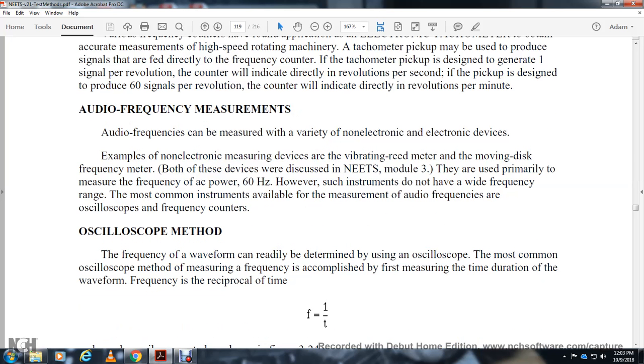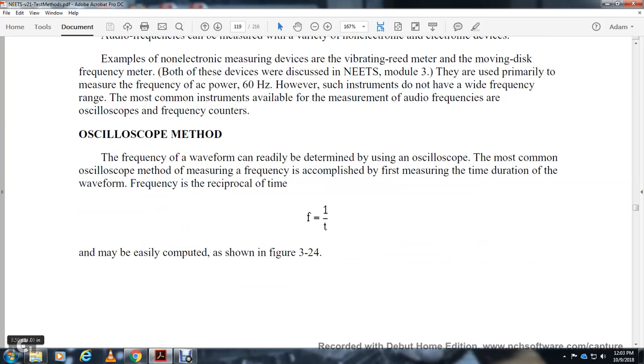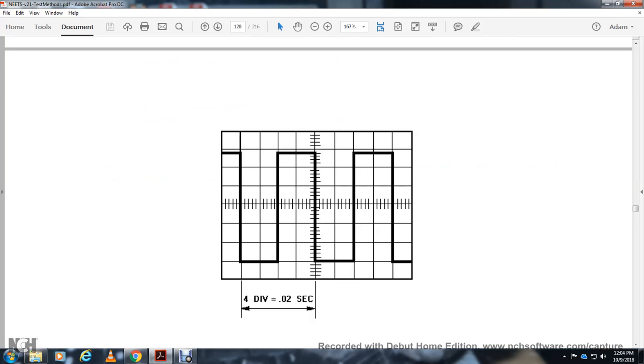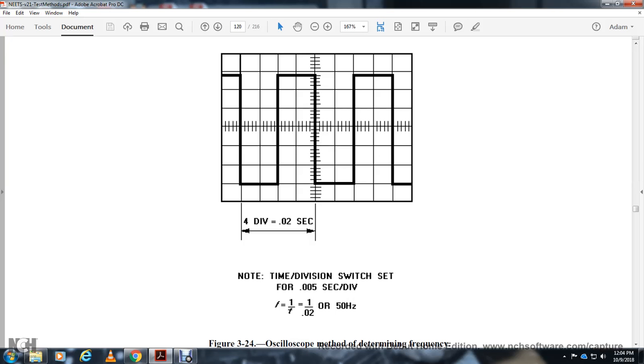Oscilloscope method. The frequency of a waveform can readily be determined by the oscilloscope. The most common oscilloscope method of measuring frequency is accomplished by first measuring the time duration of the waveform. The frequency is the reciprocal of the time, frequency equal to 1 over the time, and may be easily computed. In figure 3-24, there are 4 divisions at 5 thousandths of a second per division, so the time is 0.02 seconds. Frequency is 1 over the time. 1 over 0.02 will give you 50 hertz.